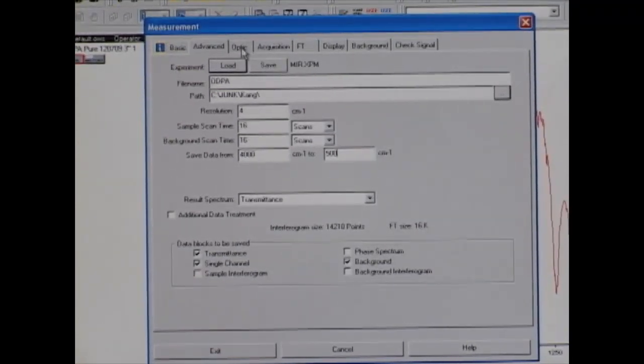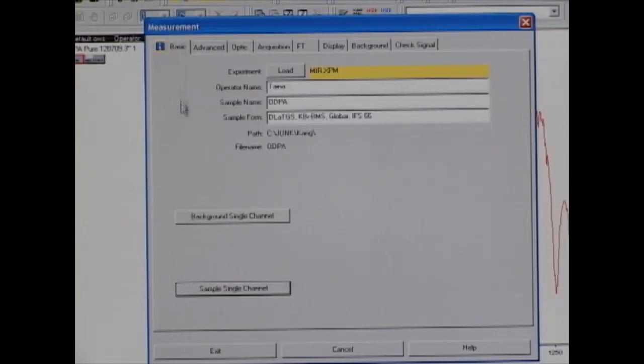After that, we move back to the Basics tab. In the Basics tab, the first thing we're going to do before we load our sample is to run a background scan of the salt plates that we are going to use.